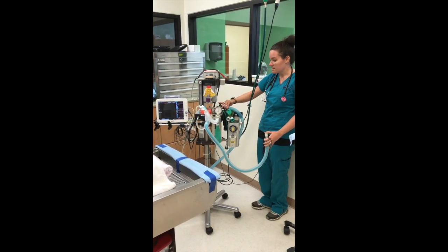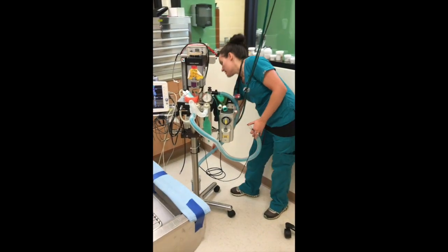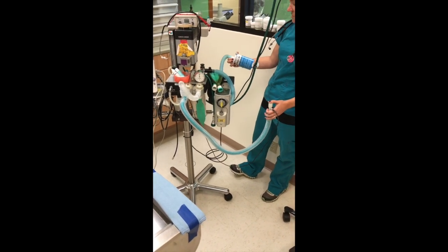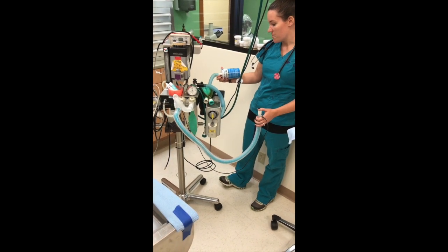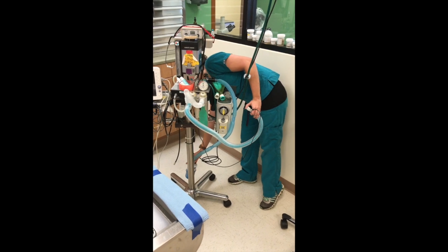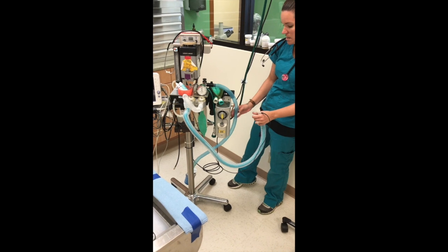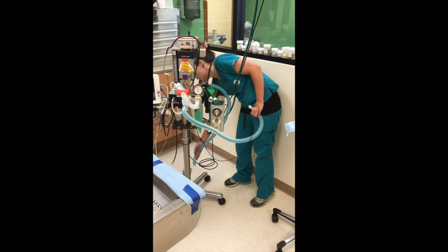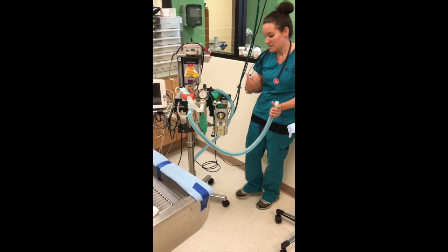And then this is our relief valve and our pop-off valve. This goes down into an F-air canister, which sits in a holder down below. This is our scavenging system. It removes the isoflurane from the gas before it's let back out into room air. That does need to be weighed on a regular basis and replaced on a regular basis. It has to do with how much weight it gains as far as when it needs to be replaced.